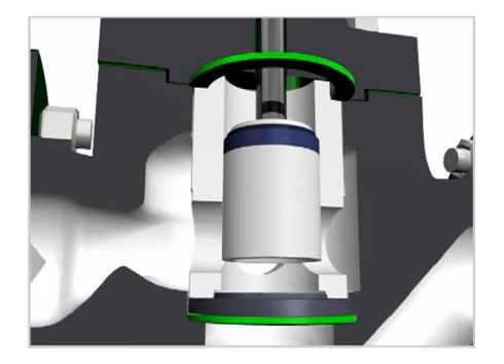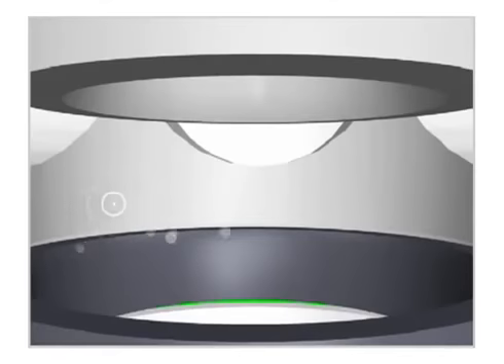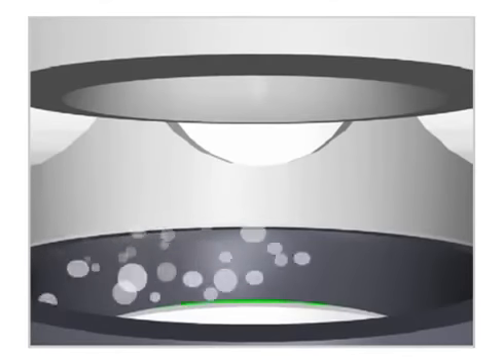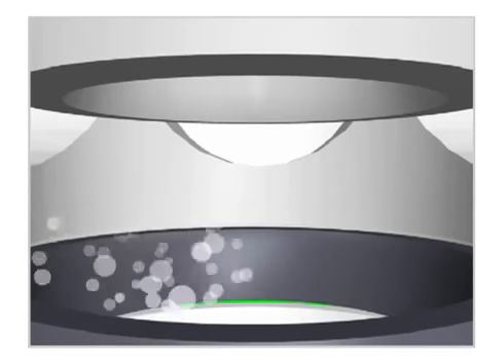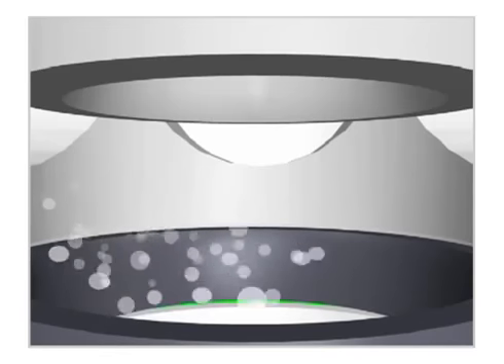The point of maximum velocity and minimum pressure is called the vena contracta. Vapor bubbles form in the liquid when the pressure falls to near the level of the liquid's vapor pressure. When the pressure recovers downstream, the vapor bubbles implode and return to liquid form.